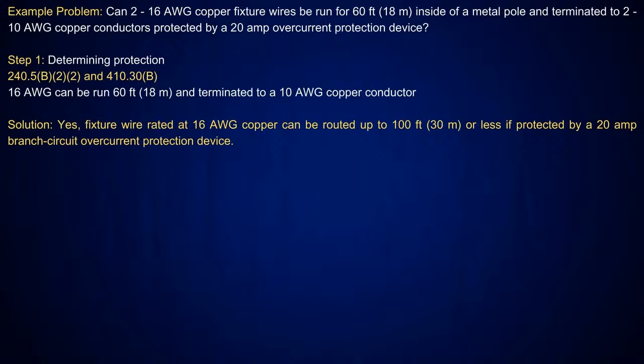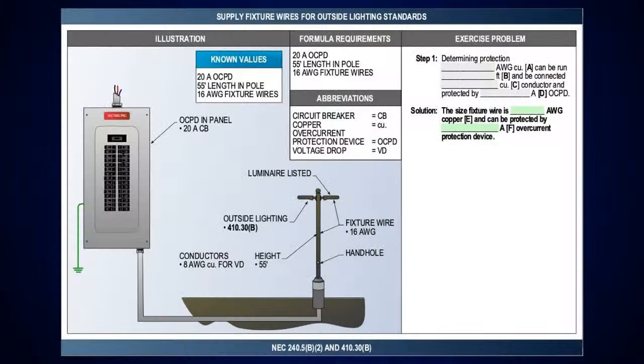Right. Okay. But I can see what you're saying. Some say I can tap here and go up and feed all this. Well, I look at it more as they're nothing more than fixture wires. Okay. Right. And then here's one here. You got number 16 fixture wires with a 55 foot length pole with 20 amp overcurrent devices. What size conductors are going over there?